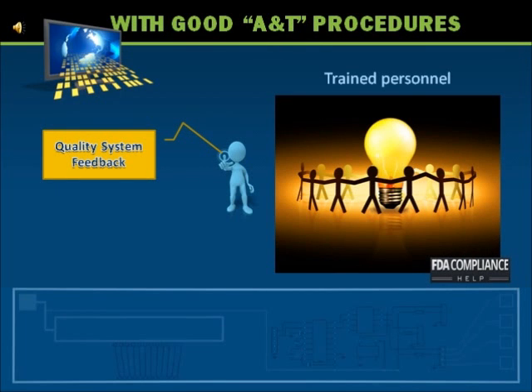If the facility has adequate test and inspection procedures and these are used by appropriately trained personnel, then there is a high probability the devices will meet the company device specifications for acceptable product and assure it is fit for intended use. Further, the data collected during in-process or completed device evaluation should be appropriate, complete, and correct. The data shows the good and bad points about the product and specific production activities.